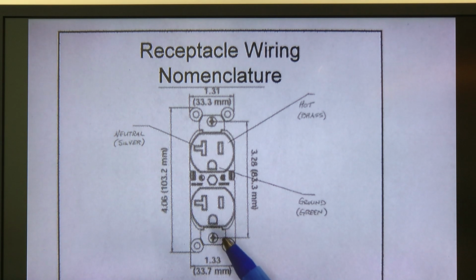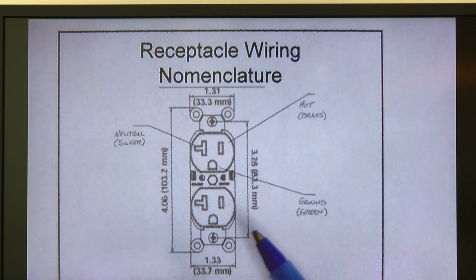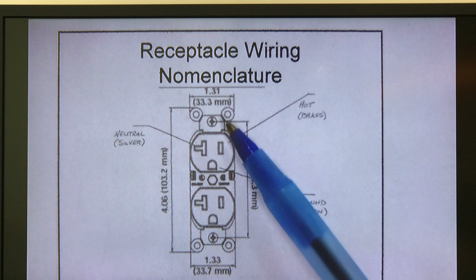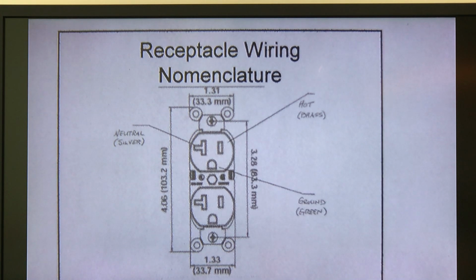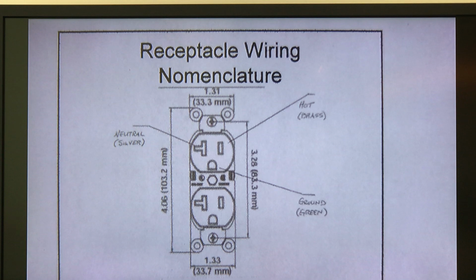Typically, this might even be painted a kind of a green color on the screw where you make the attachment. The ground connection goes to the little metal frame that supports the receptacle body, and that in turn is connected to the internals of the power outlet box. Sometimes there's a conduit ground, mostly there is in new construction. And so it's a safety connection, and we'll talk about its requirements here in just a little bit.